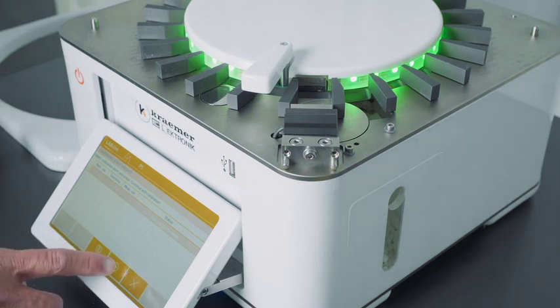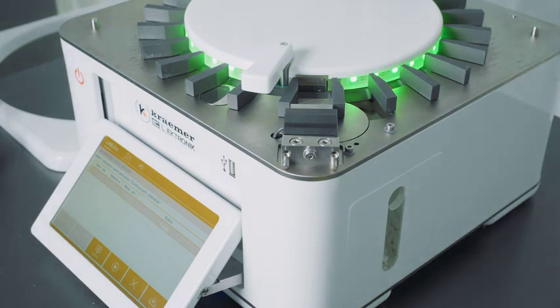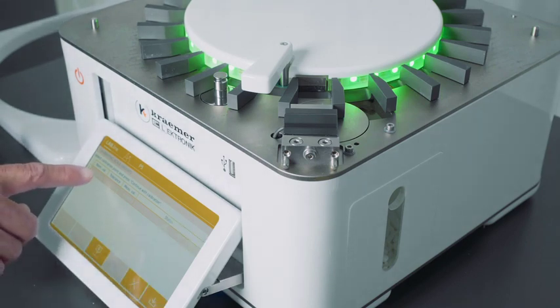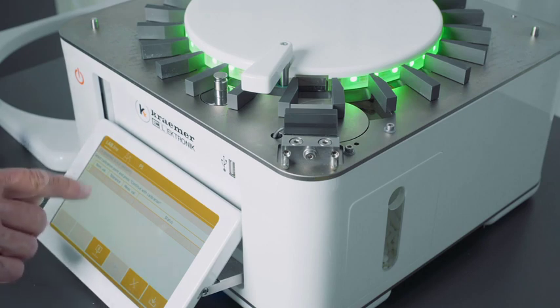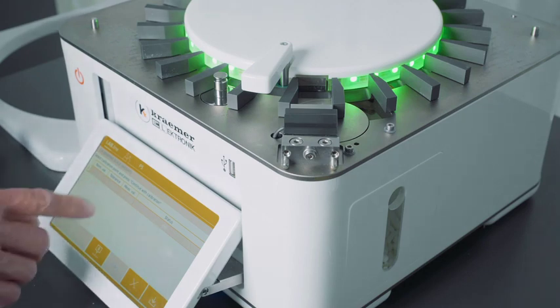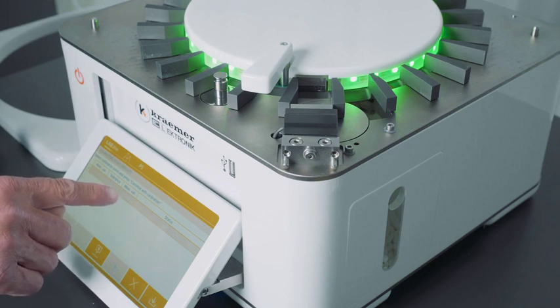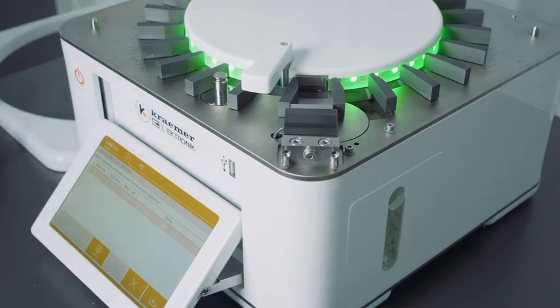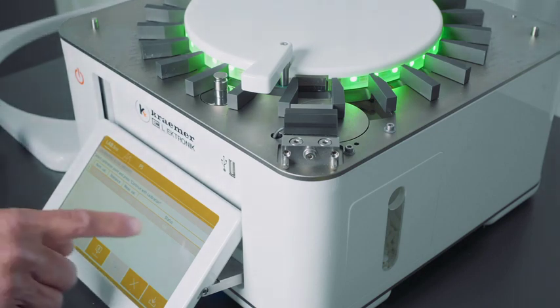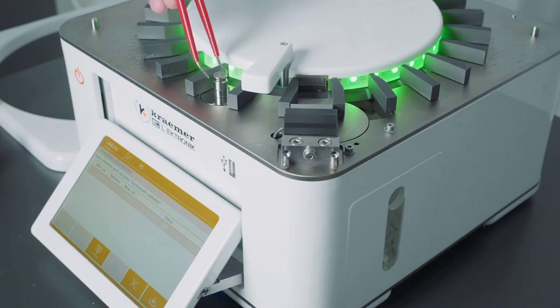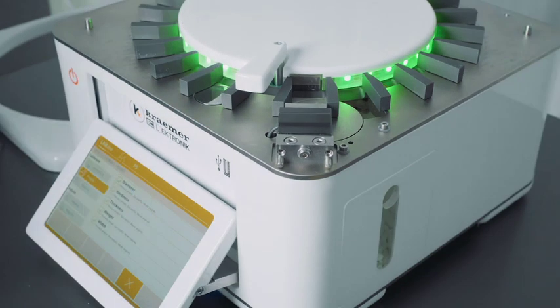and we say calibrate. It has failed because there is no calibration weight on the balance. Now I put the weight onto the balance and try again. And now you can see the nominal value is 10 grams. The tolerance is plus minus 1 milligram. The measured value is 10.0002. That means it is within tolerance and the status is OK. Calibration is successful. Next we will verify the thickness calibration.